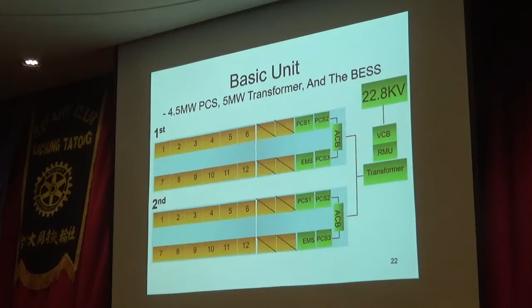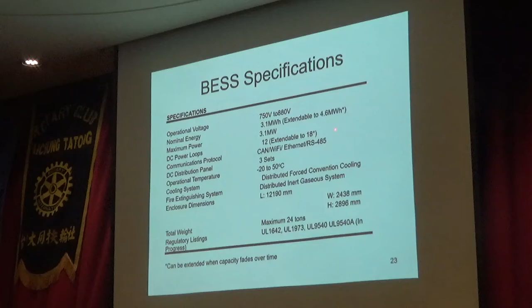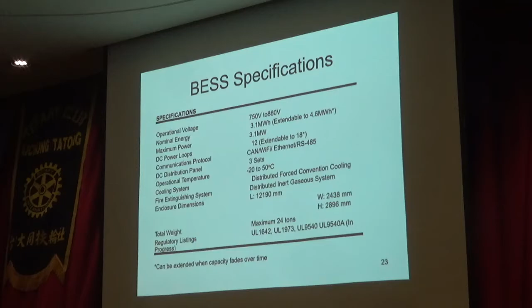For each container, it has 3.1 extendable to 4.6 megawatt hours, so the capacity is pretty big. Like I said, safety will be a major issue in creating big systems. It's about 880 volts maximum, oscillating between 750 to 880 for mitigating grid quality.